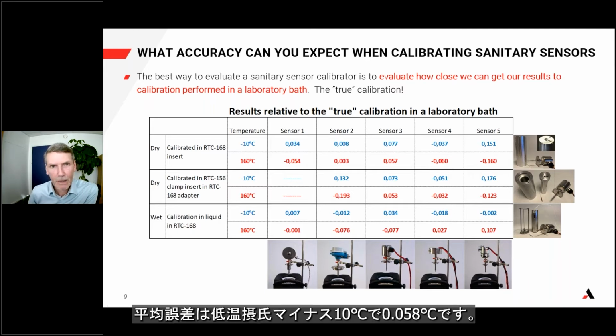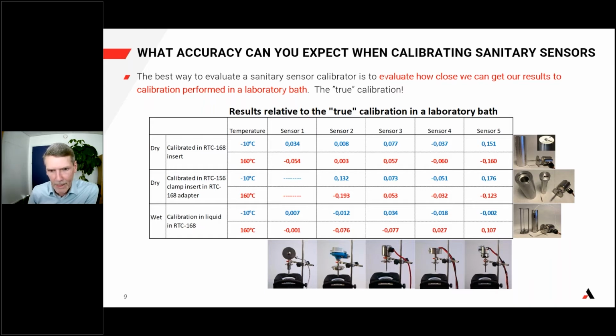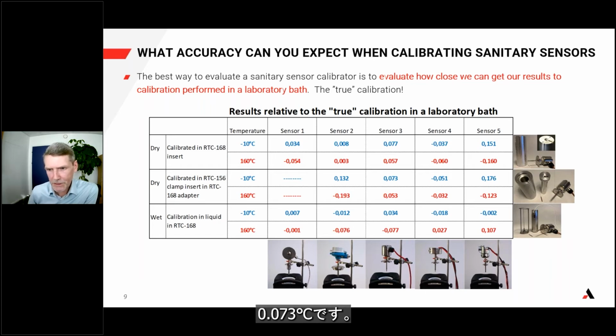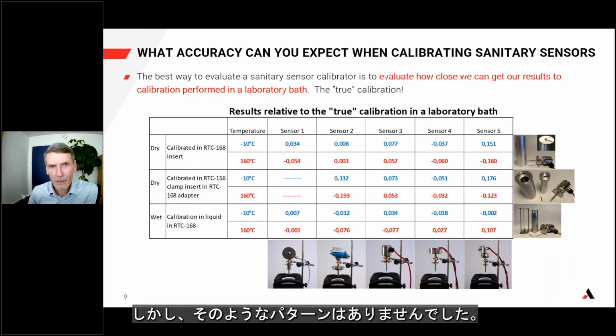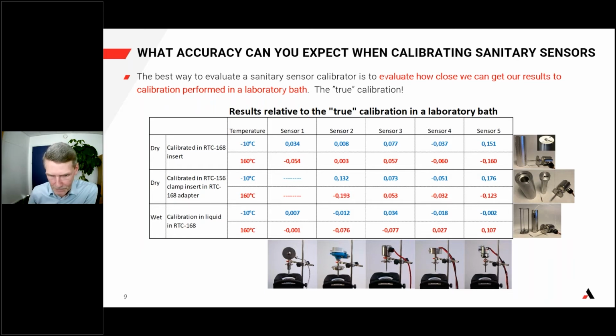So relative to the true calibration in a bath, we find that the average error at the low temperature, -10 degrees, is 0.058. And the average error at the high temperature, 160 degrees, is 0.073. Furthermore, I have searched to find a pattern to recommend a special calibration scenario for certain types of sanitary sensors, but there is no such pattern.